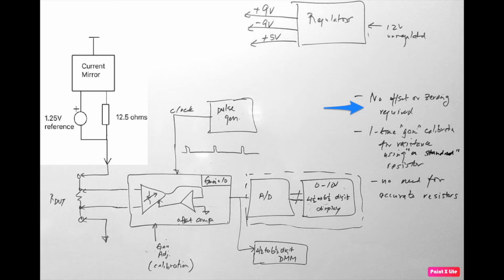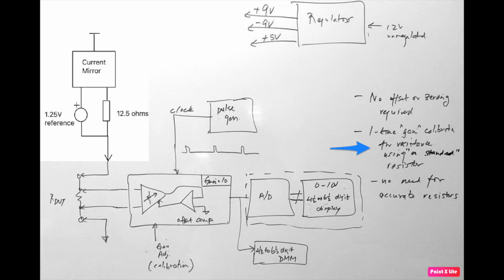So to conclude the presentation of the block diagram and to highlight the main features, there is no offset or zeroing requirement for this milliohm-meter. It's very easy to use that way. There is only one-time gain calibration using a standard accurate resistor like a 1 ohm or whatever value under 10 ohms that you can find, and that's all you need. And the third is that you don't need accurate resistors or accurate currents because you're going to be calibrating against that accurate or standard resistor one time, and any offsets or any drift are basically taken care of by the circuit itself.